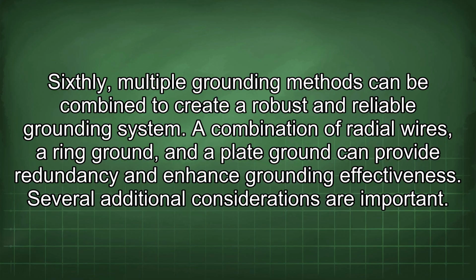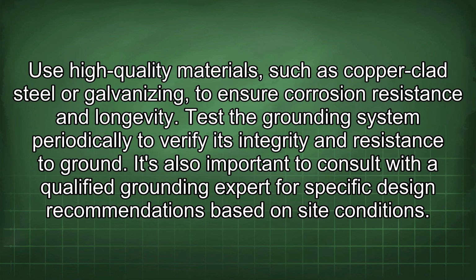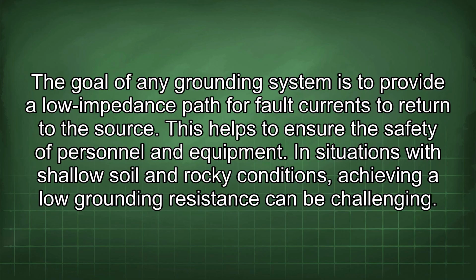Several additional considerations are important. Use high-quality materials, such as copper-clad steel or galvanizing, to ensure corrosion resistance and longevity. Test the grounding system periodically to verify its integrity and resistance to ground. It's also important to consult with a qualified grounding expert for specific design recommendations based on site conditions. The goal of any grounding system is to provide a low impedance path for fault currents to return to the source. This helps to ensure the safety of personnel and equipment.